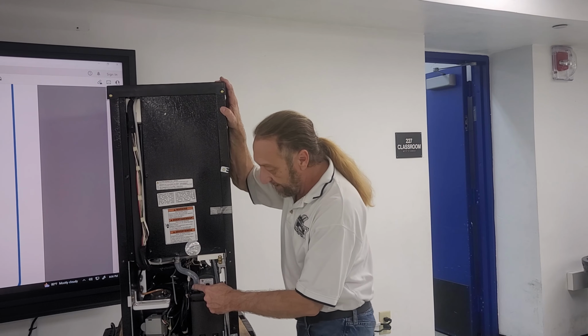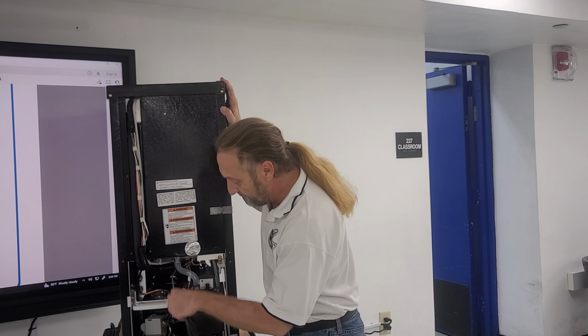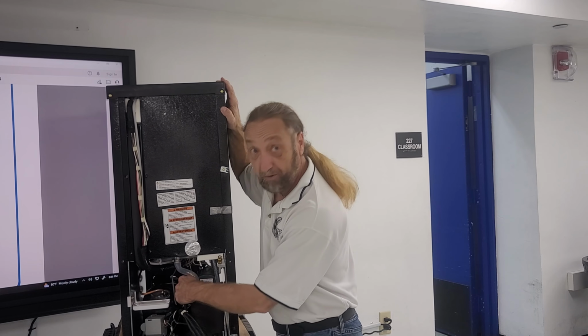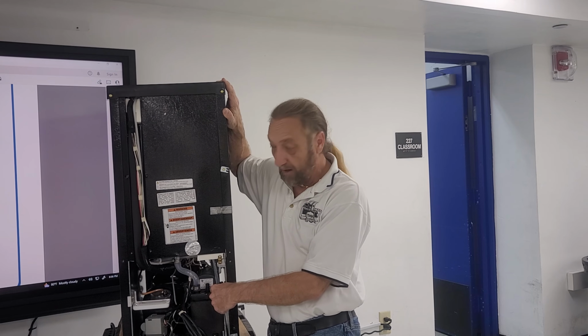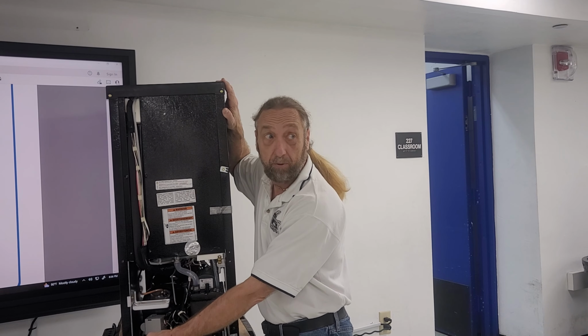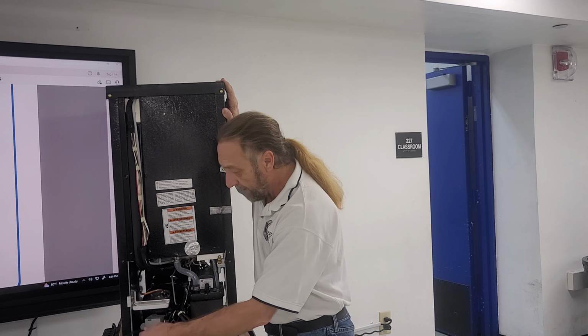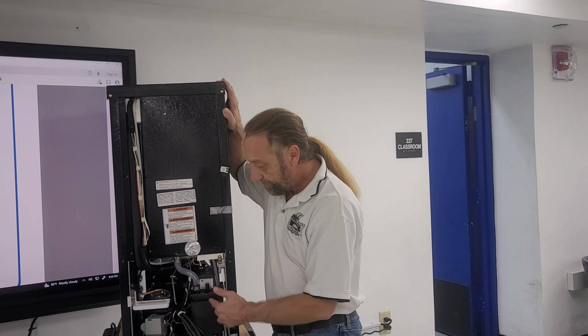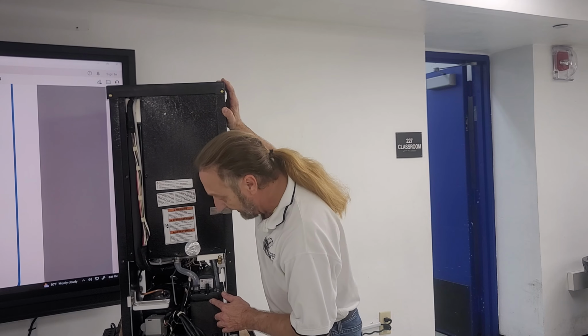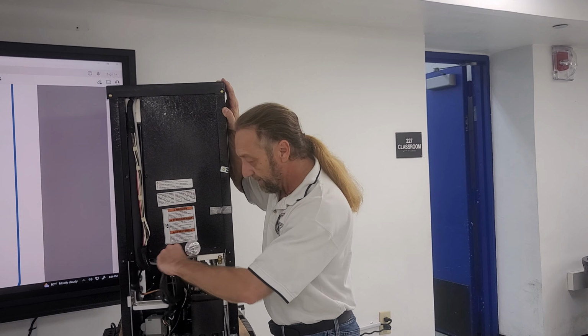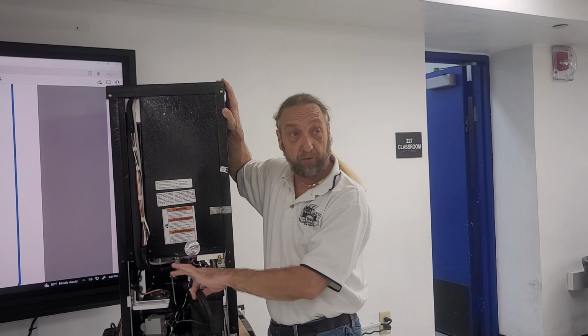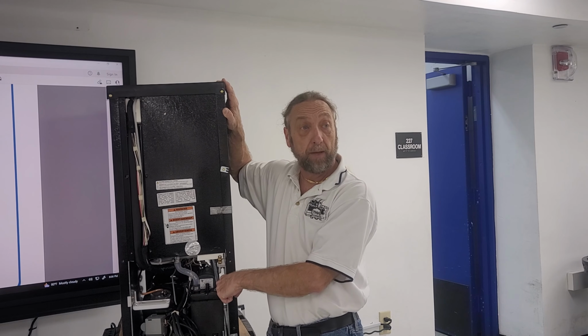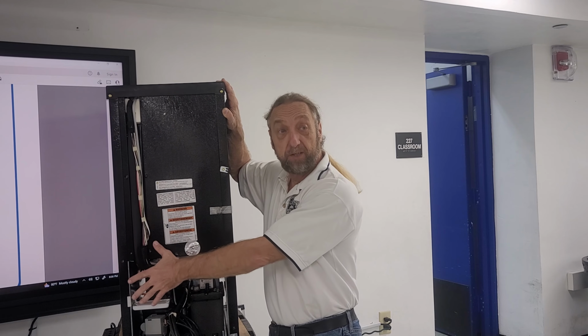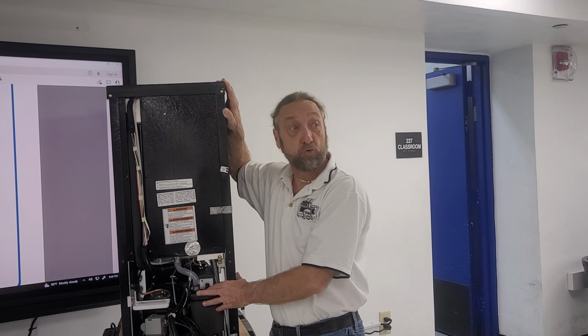So you just disconnect this. One thing I want you to notice, which is important, is there's a plug right here plugged into this condensate pump, but yet we have a plug going out here that goes to the wall. This plug is connected to the condensate pump, then the machine itself - this is the wiring harness for the machine - is plugged into the pump. And that's how this pump will shut this machine off if it's not draining.